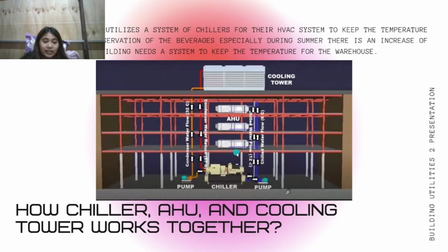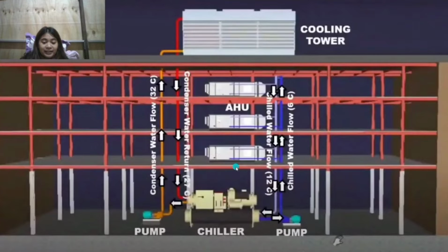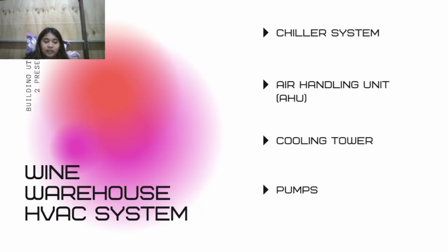The wine warehouse utilizes a system of chillers for their HVAC system to keep the temperature needed for the preservation of the beverages, especially during the summer where there is an increase of heat gain. So the building needs a system to keep the temperature for the warehouse. In the illustration, it is a very typical setup where there is a chiller along with the distribution pumps and the air handling units and the cooling tower, which is up on the roof. So now let's proceed to the chiller system.